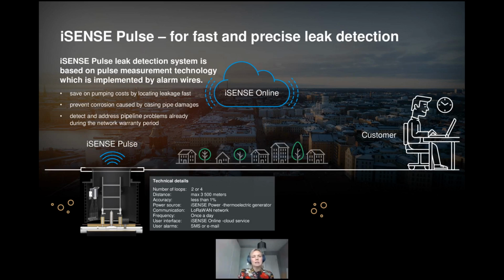What the iSense Pulse does is leak detection. It is a leak detection system which is based on pulse. Leak detection itself is not a new innovation. Alarm wires are not a new innovation. Compared to traditional systems, which are usually based on frequency measurement, we are measuring on pulse, which is a little bit newer and more precise. And what is the innovation is that we can do this underground without electricity, without any retrofit problems if you have the wires inside the pipes.